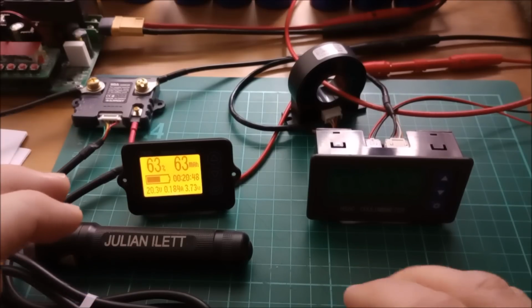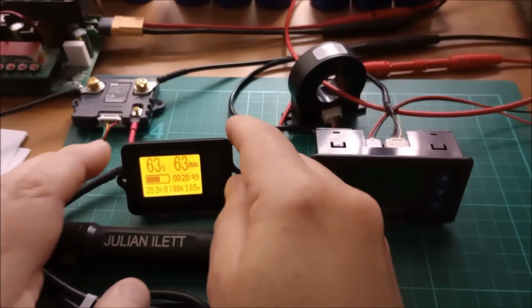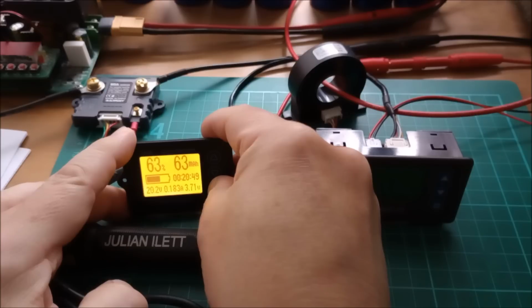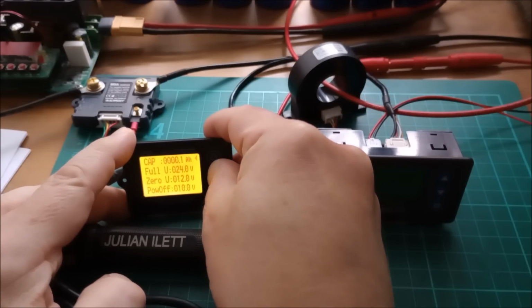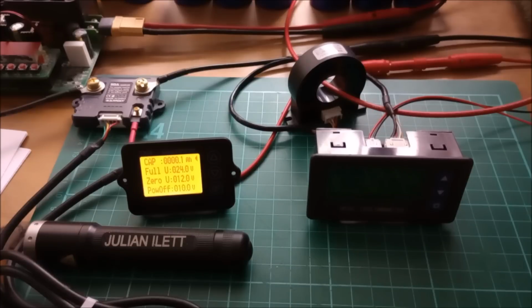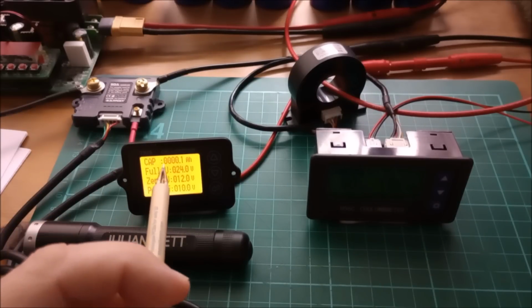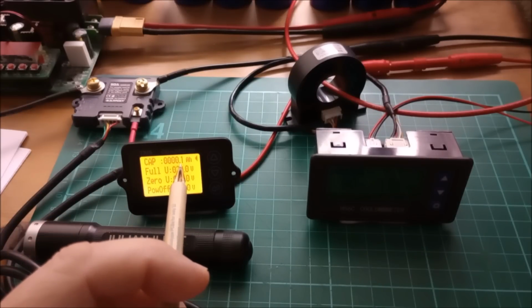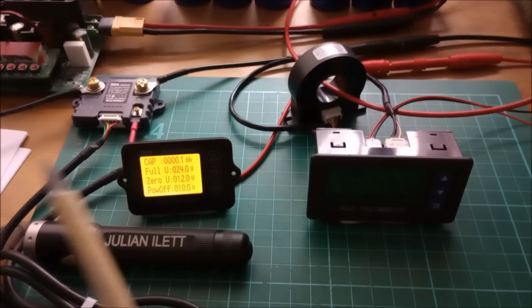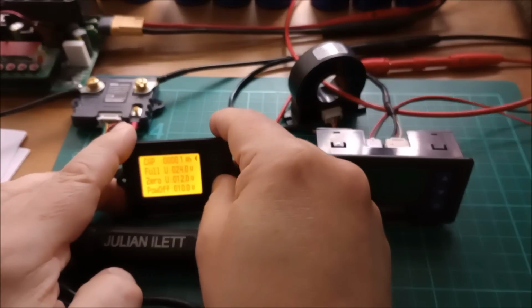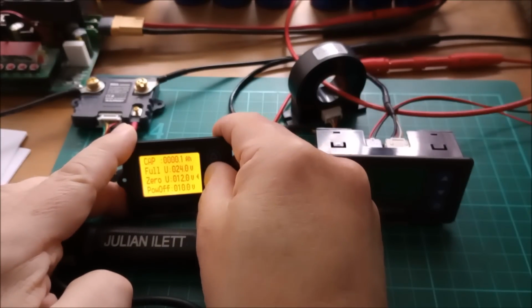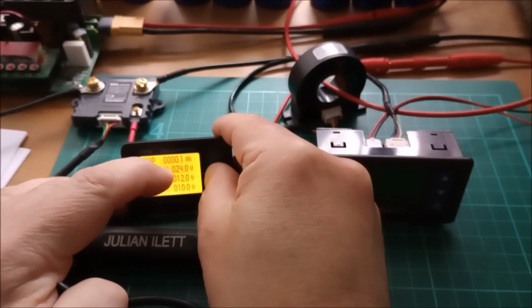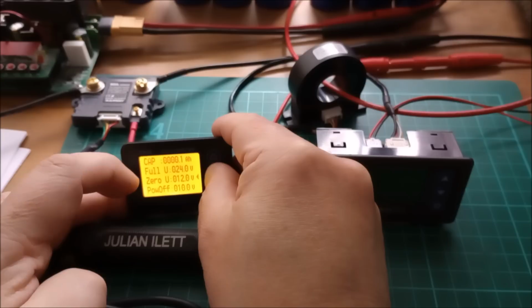Right, on my list of things to cover, weird features. The TK15, if you go into the parameters and scroll down, that's where you set the capacity of your battery. It's on its minimum setting of 0.1 amp hours, which is 100 milliamp hours. The next value up is 0.2. But if I come down through the settings, this is your full voltage trigger, 24 volts, your 0 voltage trigger...